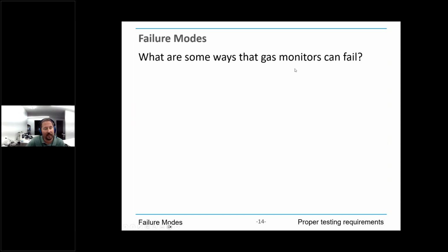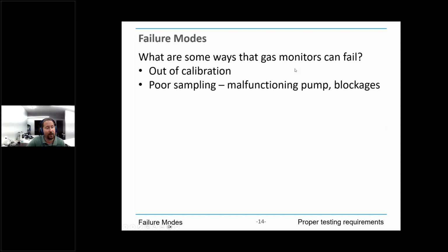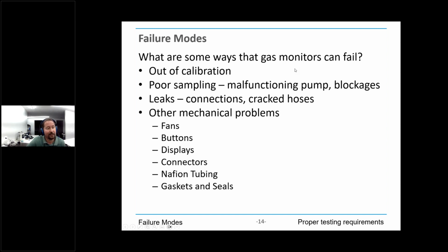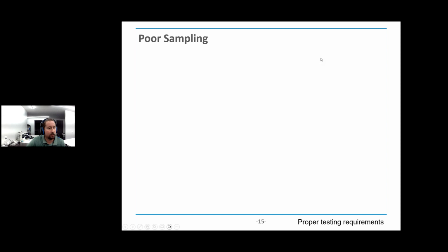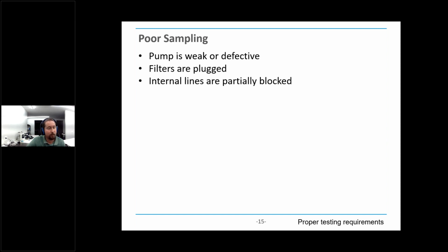So a little bit more about failure modes. They can fail in a couple different ways. The common ones are out of calibration, poor sampling, leaks, or other mechanical problems. We're going to talk about a couple of these briefly so you understand why it's important to detect these failures. So for example, poor sampling can happen because your pump is weak or defective. It can be a filter that's plugged somewhere in the system or a line that's partially blocked.